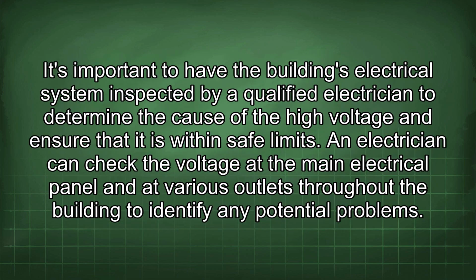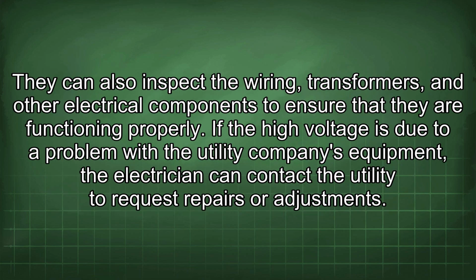It's important to have the building's electrical system inspected by a qualified electrician to determine the cause of the high voltage and ensure that it is within safe limits. An electrician can check the voltage at the main electrical panel and at various outlets throughout the building to identify any potential problems. They can also inspect the wiring, transformers, and other electrical components to ensure that they are functioning properly. If the high voltage is due to a problem with the utility company's equipment, the electrician can contact the utility to request repairs or adjustments.